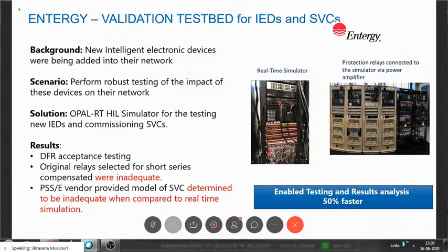So, especially from a larger grid perspective, how do we keep the system intact so that the response - taking a frequency response perspective, the generator response - is the same as studied at installation and commissioning? For that we need detailed models at the time of installation. Vendors typically provide the models, but over 5, 10, 15 years, the simulation software gets updated, and the people who developed the models move on to different places. So it's not seamless - you have to change across multiple versions, and we're not always sure what is happening. This is an issue that always exists with utilities.